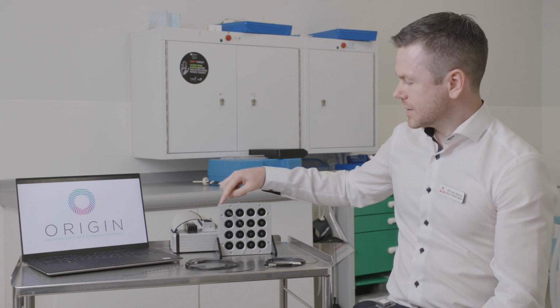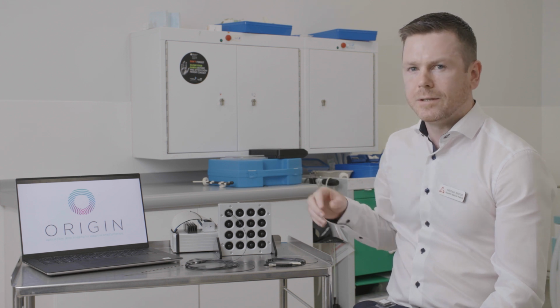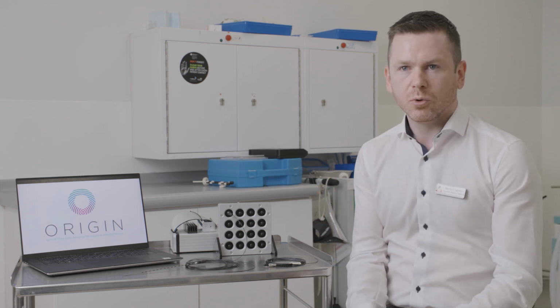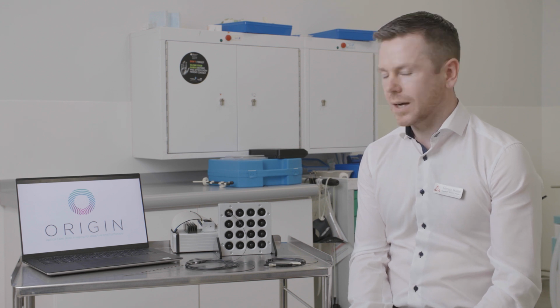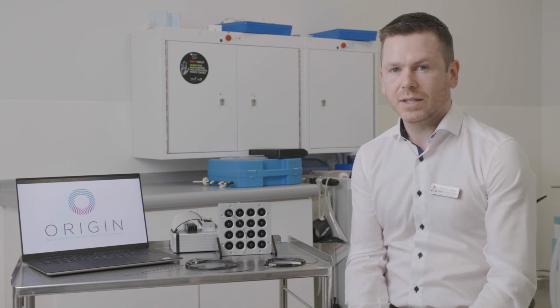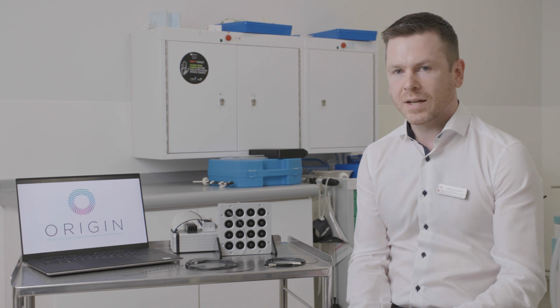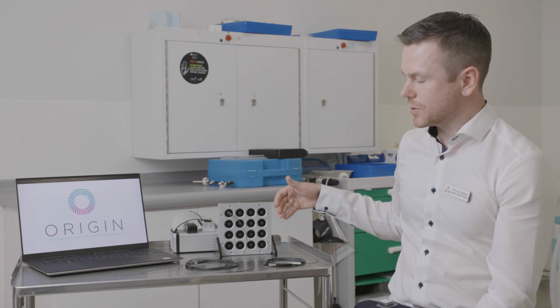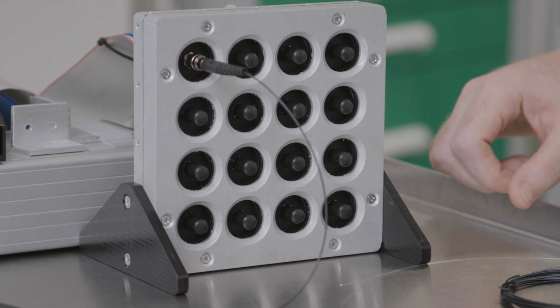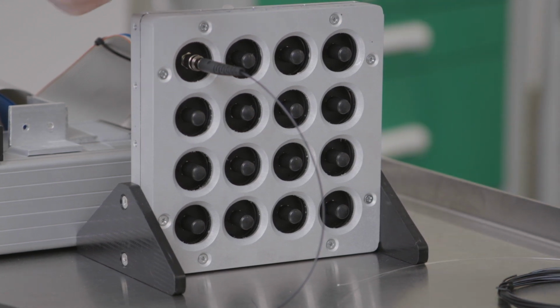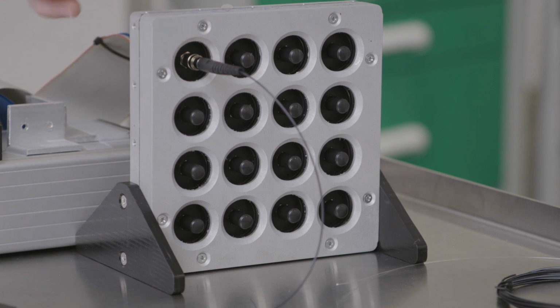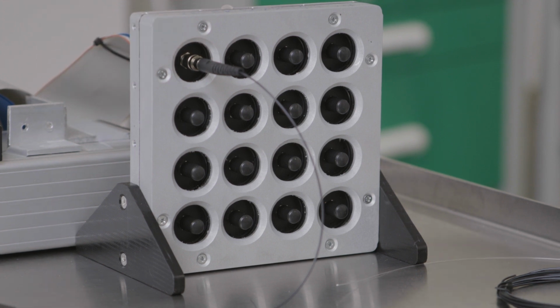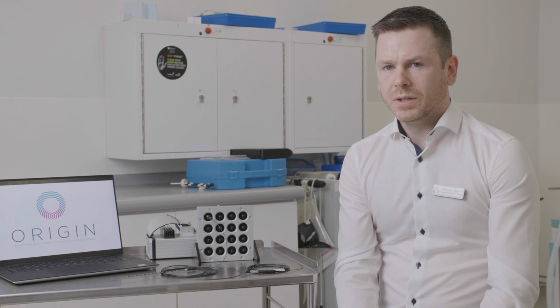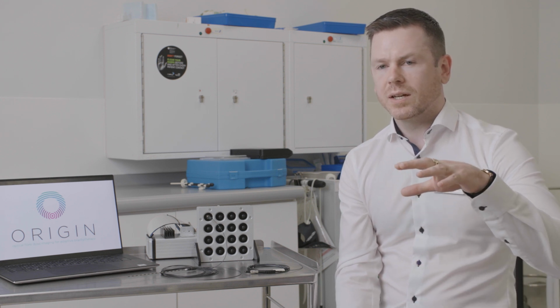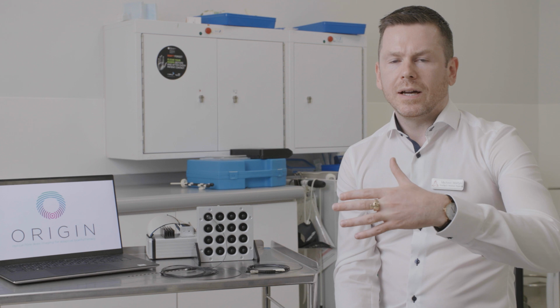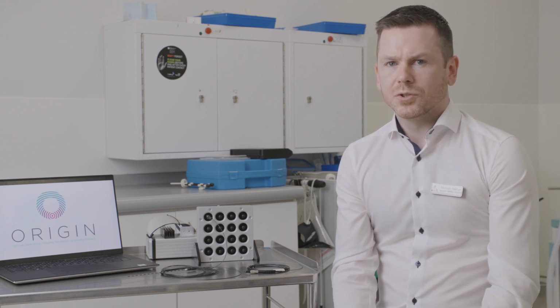As I said previously, the silicon photomultipliers that are stored in here are what we're using to count the number of photons which are emitted. They have excellent sensitivity, excellent photon detection efficiency, and small size, which, as you can see, when you consider 16 of them, the small size becomes a crucial factor in making sure that this is a portable device that could easily be integrated into a clinical environment. The fact that the Origin system allows for up to 16 optical fibres to be employed clinically means that we can measure the dose at various clinically relevant regions within a patient.